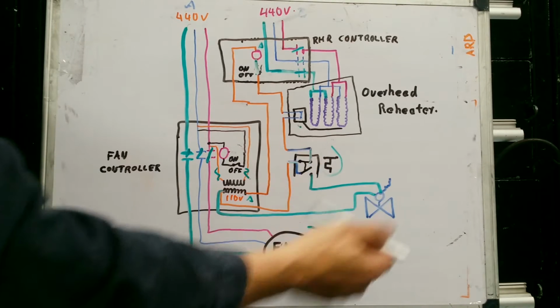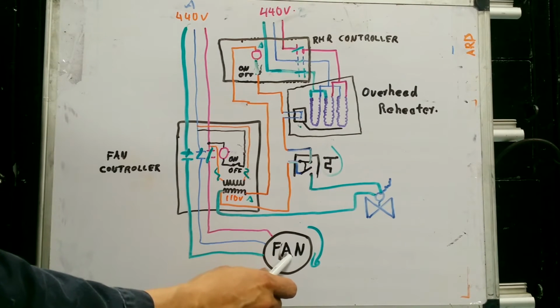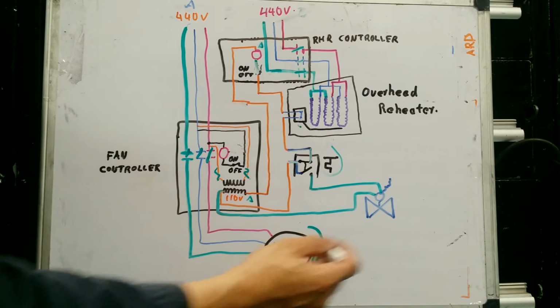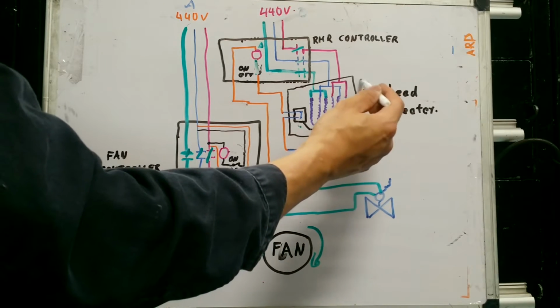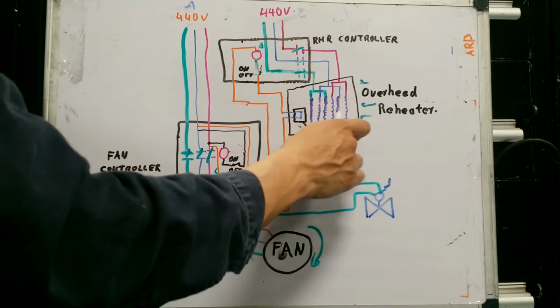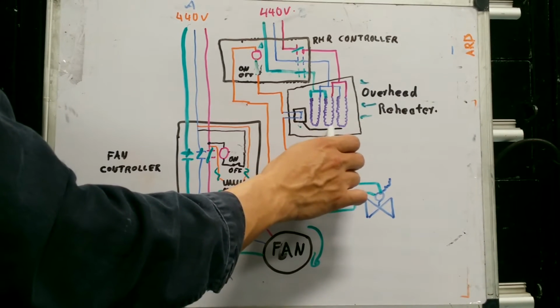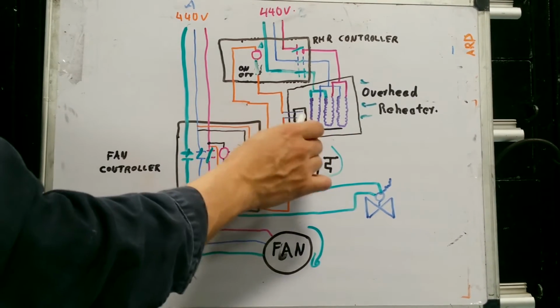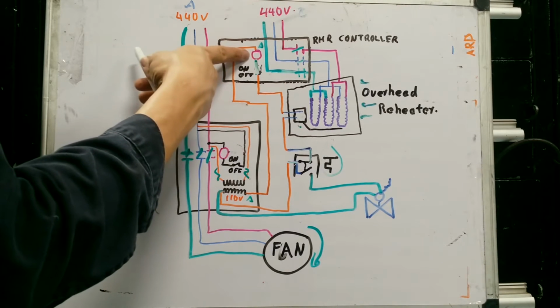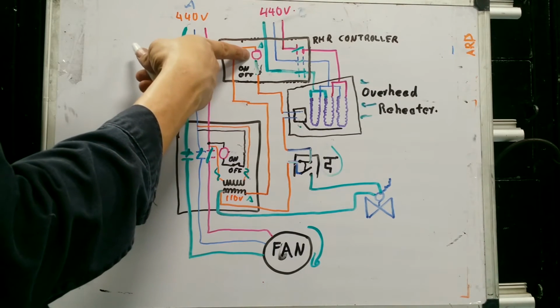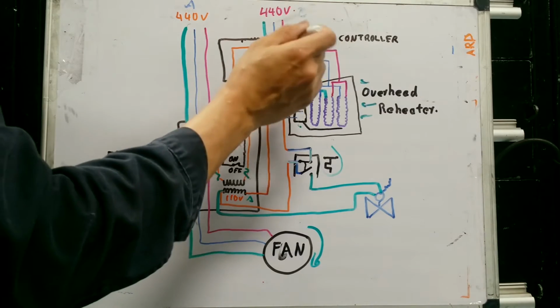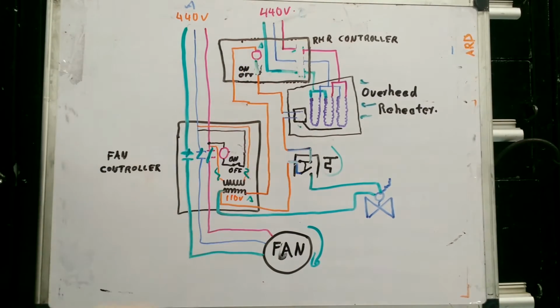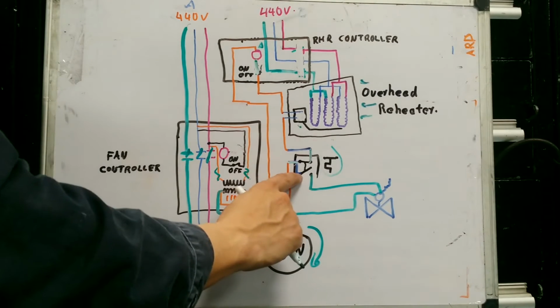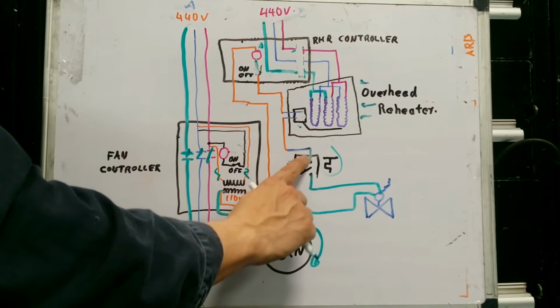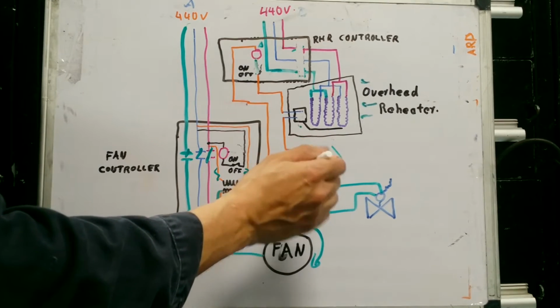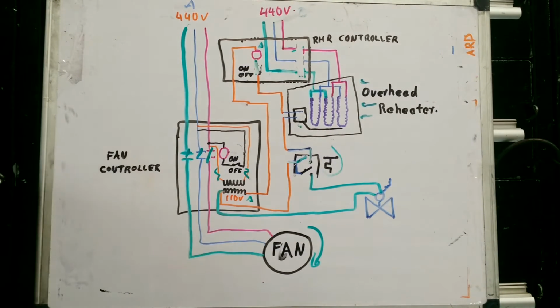If all of a sudden, for some reason, the fan just gets stuck and there is no air flow, that means there won't be air going through the heaters to remove the heat from the heaters. If the heaters overheat too much, the high temperature switch is going to open, remove power from this contact coil, and it will open this, de-energizing the heaters. If the space gets too hot, the thermostat will open, also killing power to every heater.